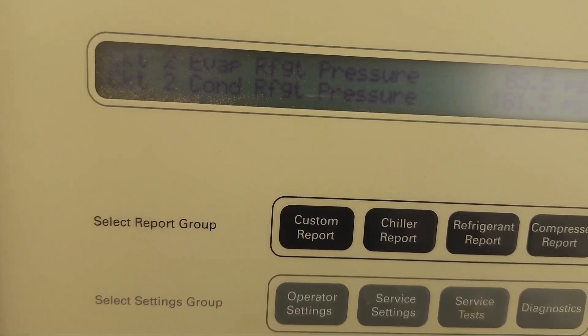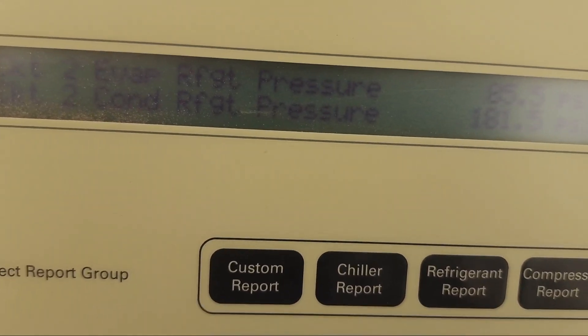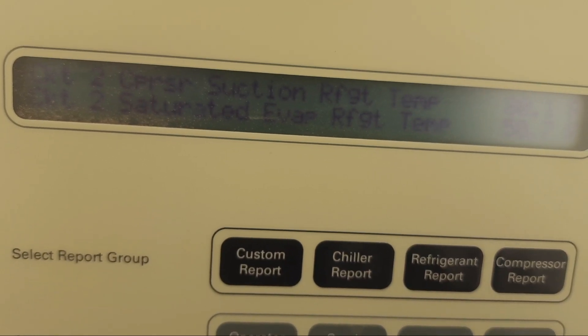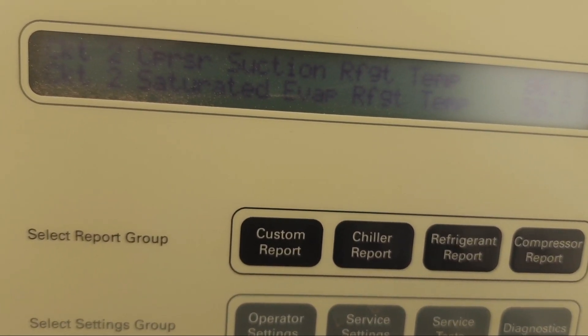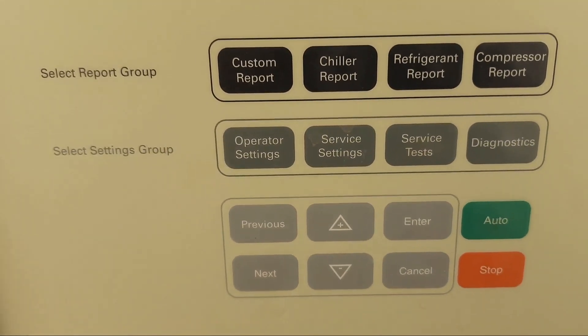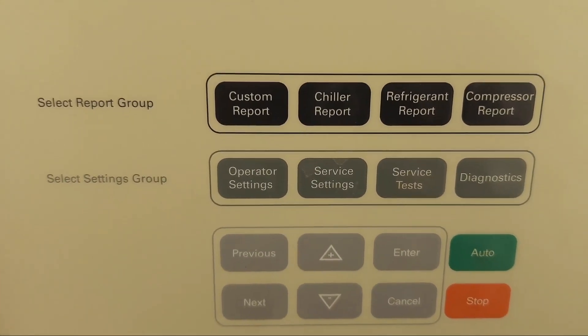Now let's go to circuit two. Circuit two evaporator refrigerant pressure is 85.5 psi and condenser refrigerant pressure is 181.5 psi. The compressor suction refrigerant temperature of circuit two is 80 degrees and the saturated evaporator temperature is 50 degrees Fahrenheit. When we press next, the saturated condenser temperature is 95 degrees. This is the static position of the chiller — the chiller is in stop position.